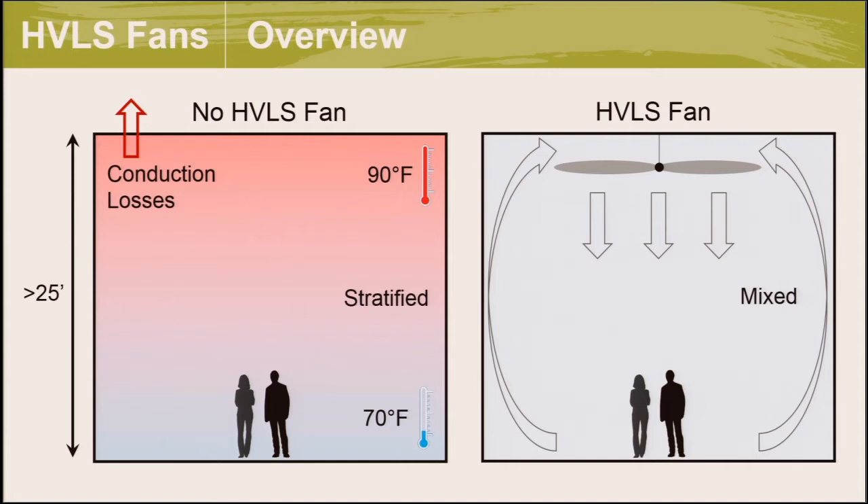Stratification causes unnecessarily high heat loss to the roof, as well as inefficient heat distribution of the HVAC system. High-volume low-speed fans increase air movement throughout the space, essentially destratifying and reducing that temperature difference from 10 to 30 degrees down to 2 or 3 degrees Fahrenheit. They're large fans, often 7 to 8 feet or more in diameter, and they move significant amounts of air slowly. Other benefits include minimal maintenance and increased occupant comfort and productivity.